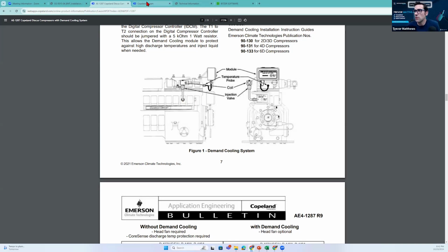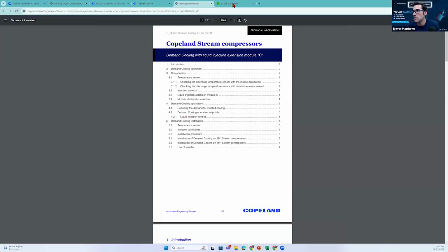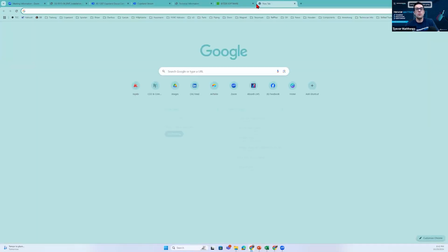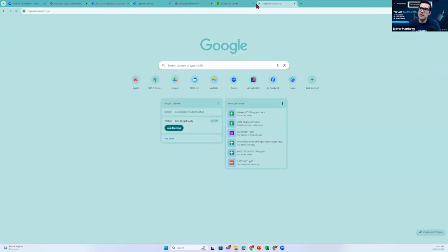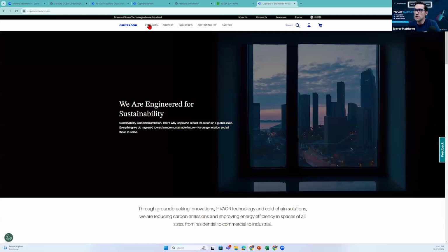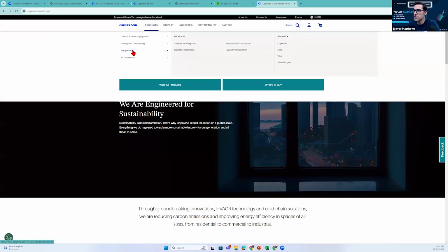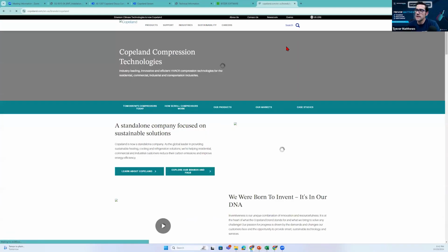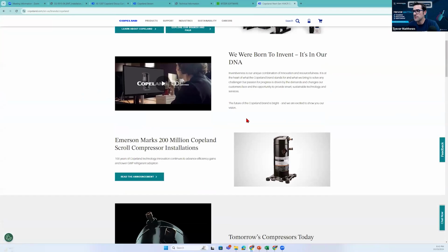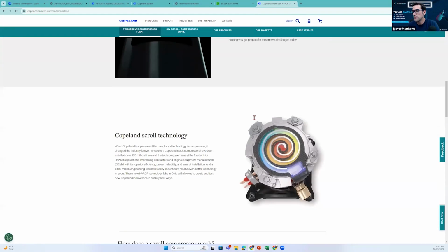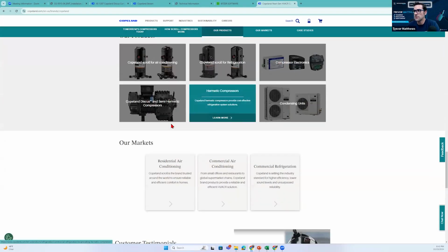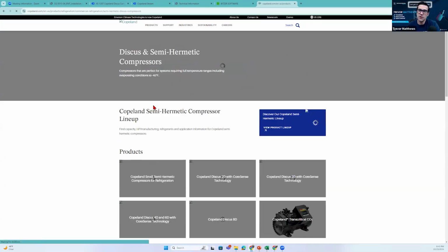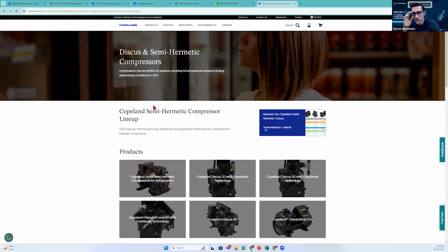And then now if you want to find out the European one, I'll go to Copeland and show you how to do it. Copeland.com. So if you're in the US, you go to products, you go to refrigeration, you go to Copeland, and then what you want to do is go to compressors. They got a ton of different stuff. So is it scrolling down? Yeah, you scroll down. If it's semi-hermetics or scrolls, always refrigeration. You will start to see, though, injection on and vapor injection on heat pump compressors.